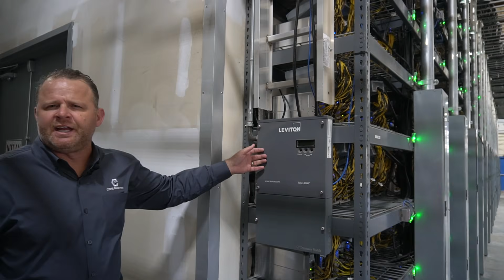So we have the meter that goes off the 4,000 from the utility company, but then we break it down to a sub-meter for billing purposes to our clients. Because we may have 10 different clients on this cold aisle, so we can break down the billing on a consumption level to each specific client. This basically has what's called a current transformer that's sitting inside the 4,000 on the breakers, and it's tied into the network.